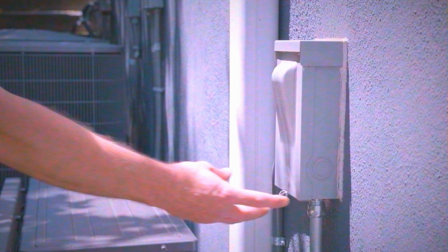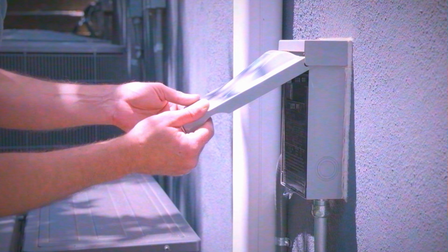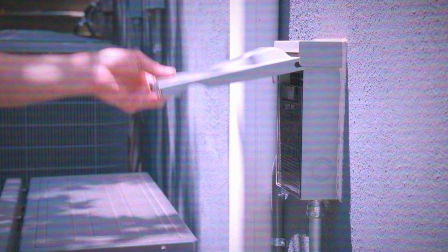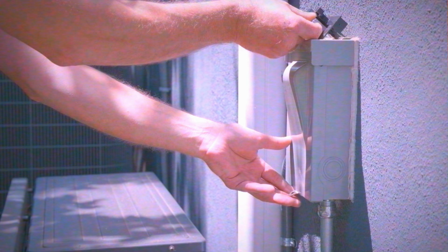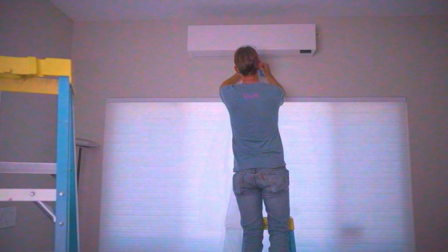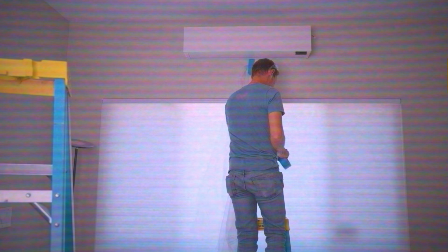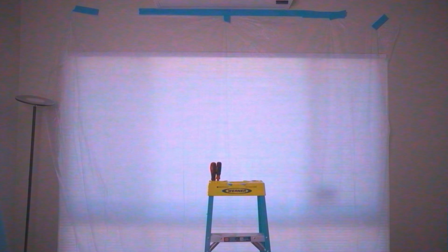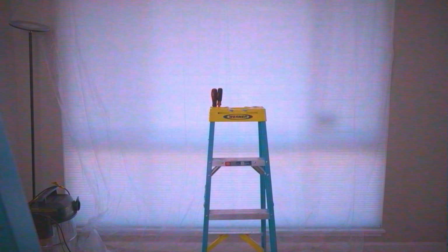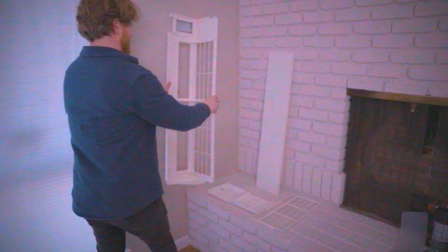Before you begin, make sure the unit is completely powered off. Use the AC disconnect and turn off power at the breaker, or, if available, the indoor unit disconnect switch. Let the unit cool down before touching any components. Set up a ladder directly in front of the indoor unit. As you remove components, place each of them in a safe and clean area.